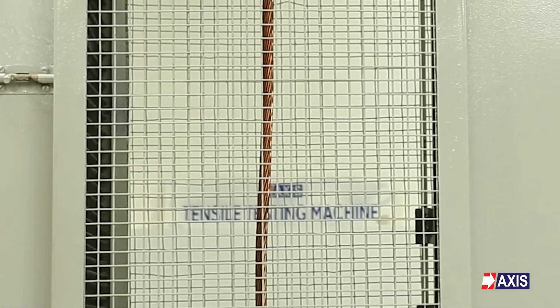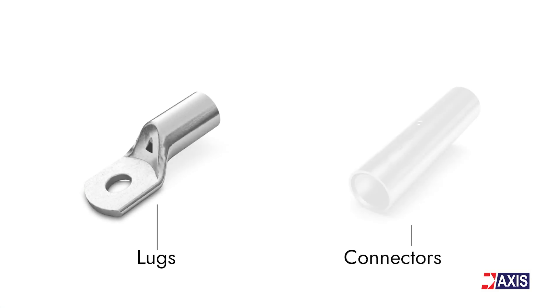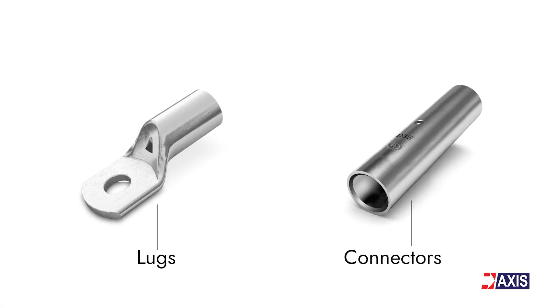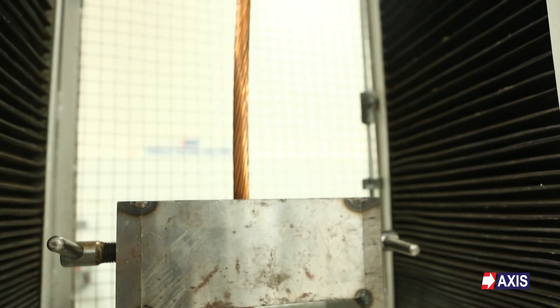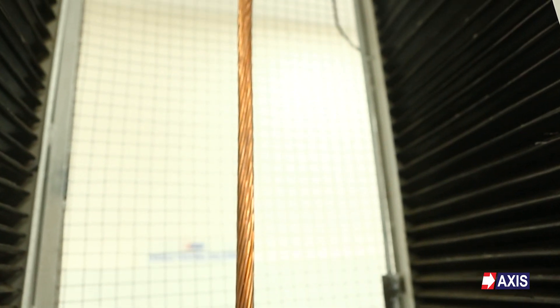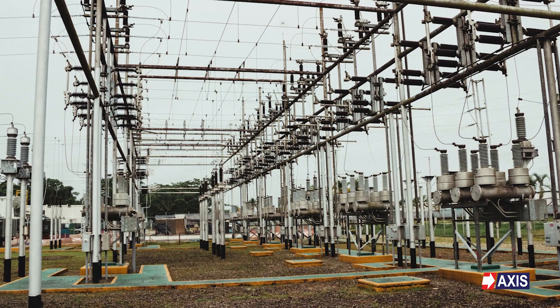In this video we will explore how the tensile test is carried out to make sure that crimped lugs or connectors are capable of carrying the required tensile load. This is tested as per the international standard IEC 61238. We will perform the test on cable lugs which are used as terminations for conductors in electrical applications like power and distribution lines.